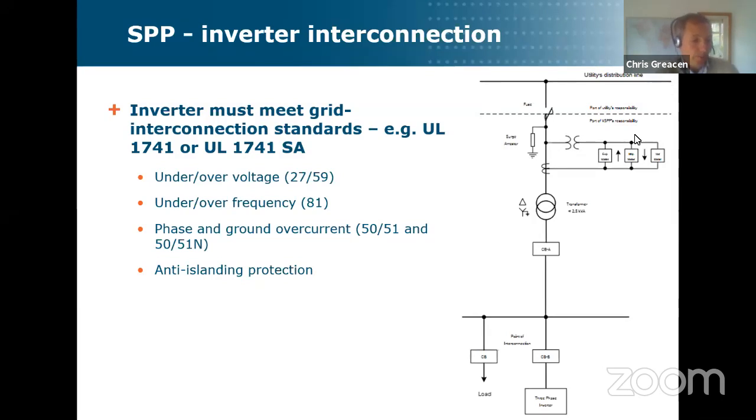This actually came about, in my understanding, because in Germany, there was so much grid-connected solar that engineers started to notice, oh, actually there would be a problem if we had a slightly low frequency event and then all of the solar disconnected all at once, we'd go from a small problem to being a really large problem. And so over the past decade or so, there's been a move to change the standards for these inverters so that they can keep providing electrical support in the event of certain types of abnormalities.